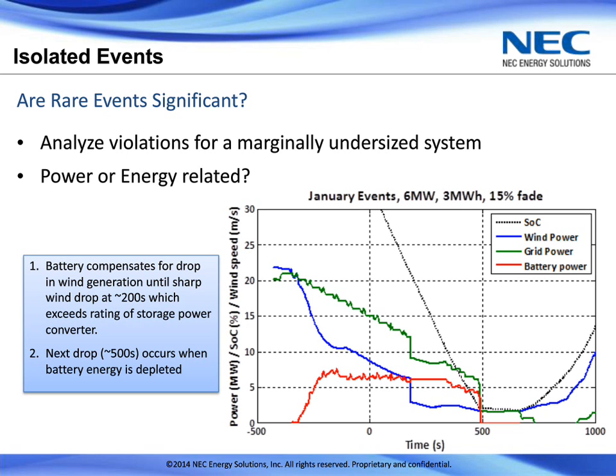There's a further problem that at about 500 seconds, because of the length of this event, we can see the dotted black line, which is the state of charge of the battery, has now dropped down to the point where there's no longer enough energy to continue to discharge, and so there's another drop that shows up on the grid side. So this is a single event we can look at, but we understand from here that more energy and more power would be required to meet this.